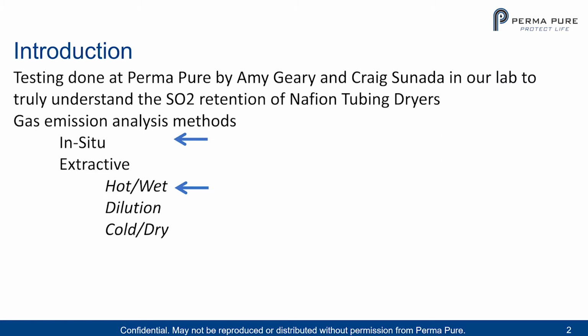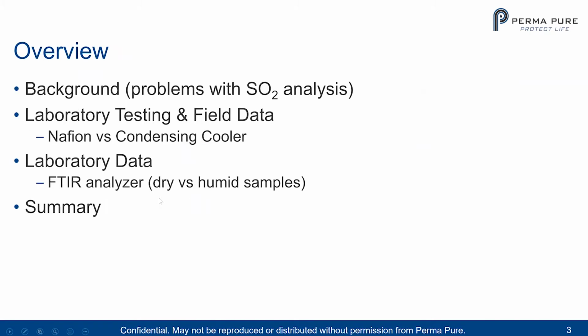And then the cold and dry extractive method, which is what we normally pay attention to ourselves, because most analyzers want the samples cold, clean, and dry, and they come off the stack hot, wet, and dirty. So one of the challenges some of the other methods have is that they run into problems with long-term reliability because of the difficulty in the actual sample itself. It's corrosive, it's dirty, it's hot, and it's challenging to get accurate measurements over time.